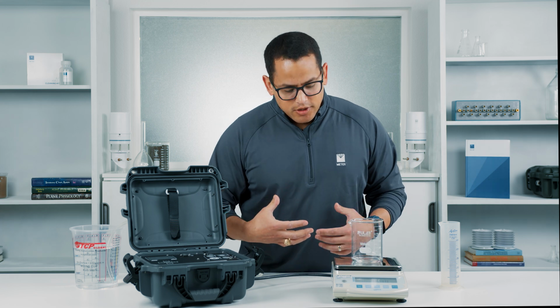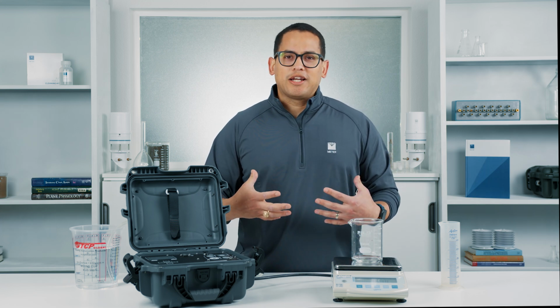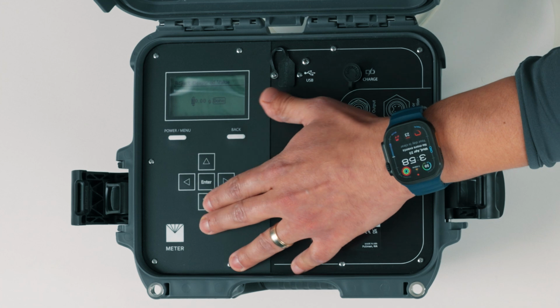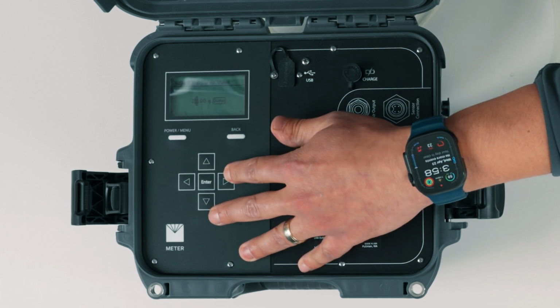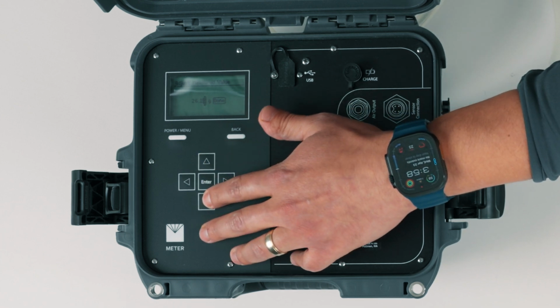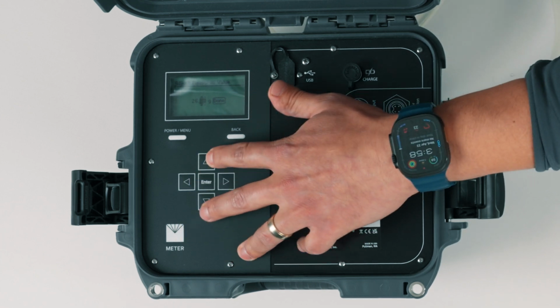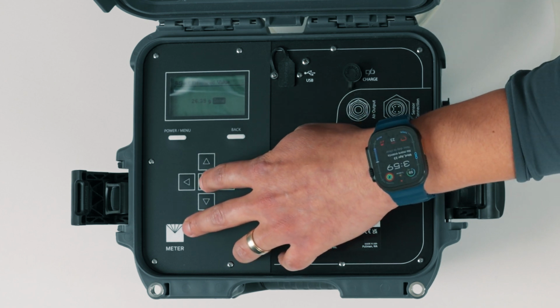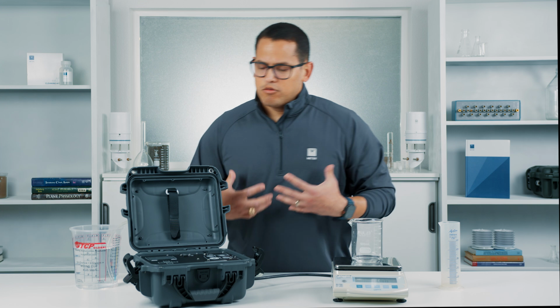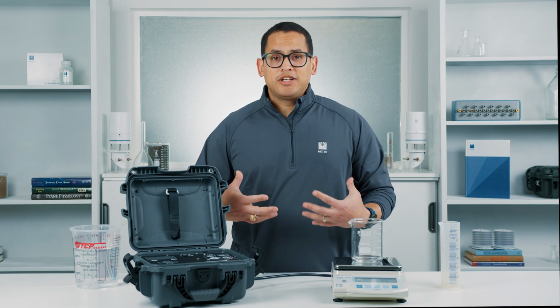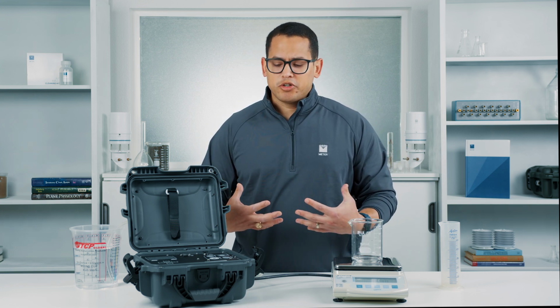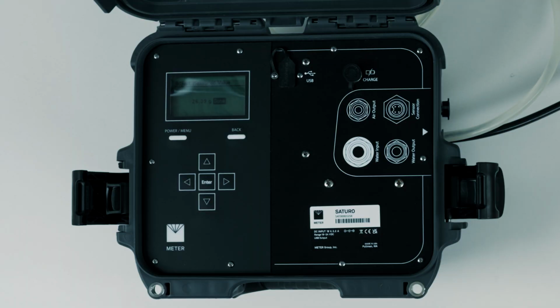You can see that's measuring about 26.39 grams. And so what we can do is enter that into the calibration screen as our volume. We know that 1 gram of water approximates 1 milliliter of water. So we'll enter that value in here, but it does come out in terms of grams. Once we have that value entered, we're going to hit the Done button, and you're going to see that it's going to purge the device in reverse to empty the lines of any water.